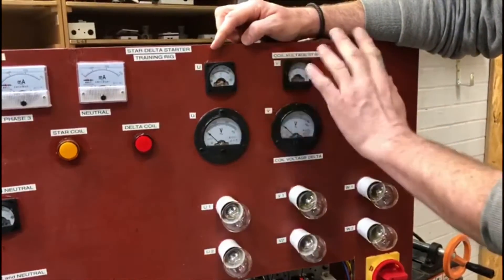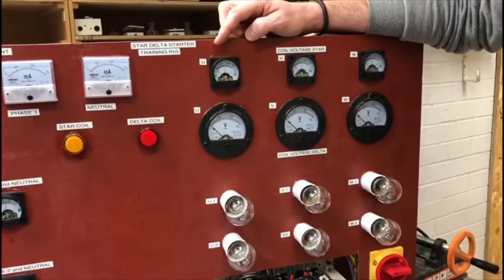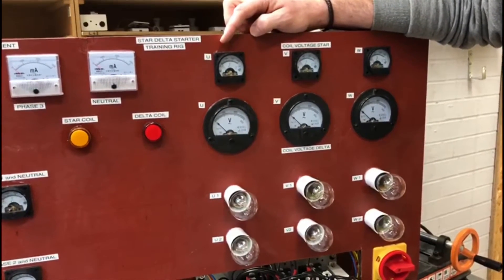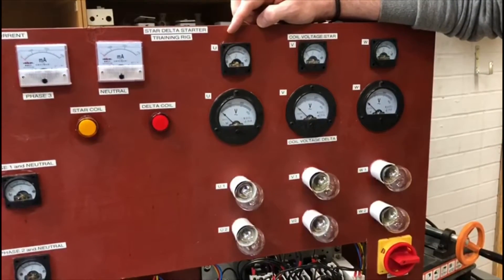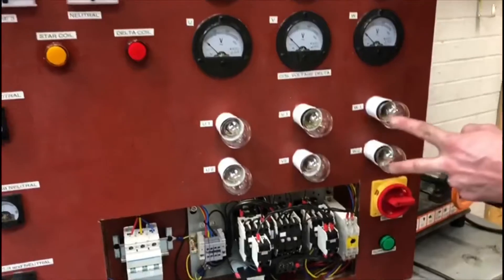These are when it comes up in star, so they should always be reading around 230 volts. These ones, however, are when it changes over to delta, which is when they are in 400 volts.